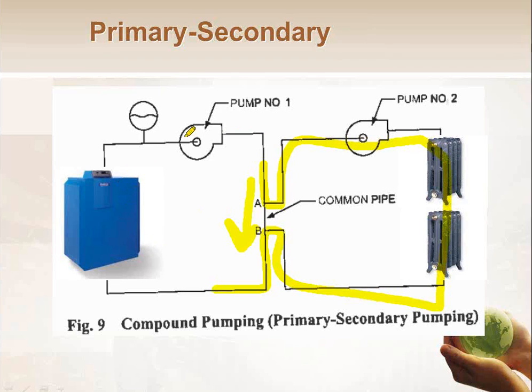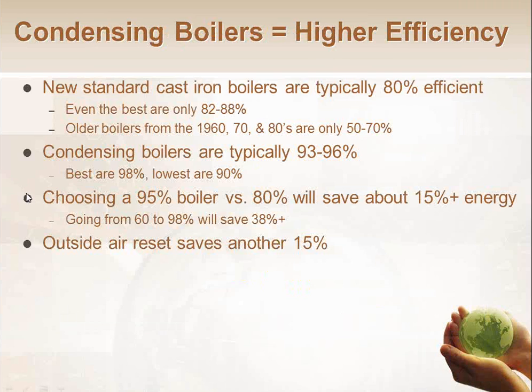So that's kind of the idea here: one pump is sized for the building, one pump is sized for the boiler, and I can pick and choose which way it goes. And as you get into more complex piping arrangements, you can have multiple secondaries and even multiple primaries. If you want to learn more about that, we have a whole class on piping and pumping that I can direct you to at the end of this presentation here. Just wanted to introduce the primary secondary piping concept for these boiler retrofits.